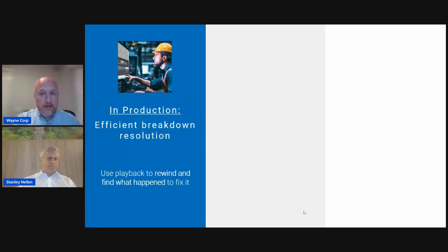Yeah, obviously when the line stoppage is identified, APB can recall up to 15 minutes of cycle data. And as we saw in the demo, we can set that data to 7.5 minutes prior or 14 minutes prior and 1 minute after the trigger event. So once we've identified a stoppage, which could be a button on an HMI or code within your application that measures the speed of the line, for instance, we can then use APB to go back through that data instantly and see what the root cause of the stop was, and how that affected the line after the trigger.